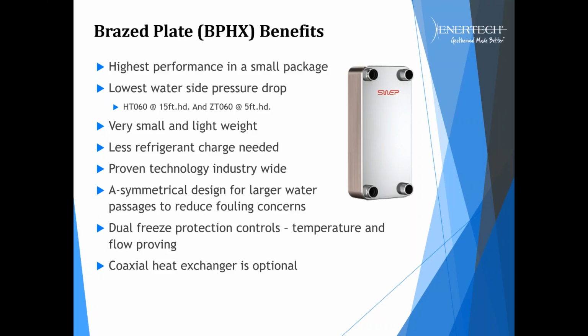The biggest change with this product that Enertech made was going to a braze plate heat exchanger. And if anybody knows anything about heat transfer and braze plates, they are superior in heat transfer versus a coaxial heat exchanger. But a lot of the industry hasn't gone to braze plates in small packaged water source heat pumps, primarily for two reasons. Number one would be freeze protection, or the fear of freezing and rupturing the heat exchanger. And number two is fouling.